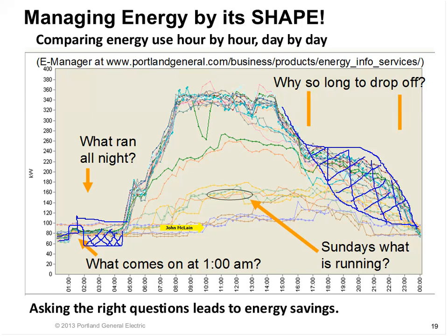And it turns out that somebody was trying to help the budget, and they said, let's rent out the facility to a church group on Sundays. So they were in there, and they would fire up all the things in certain areas, and you'd have this bump that Sundays look like this, and Saturdays you don't see that bump. Well, now you have a way to know exactly, if you're charging for that service, what does it cost us in power costs to serve that load?